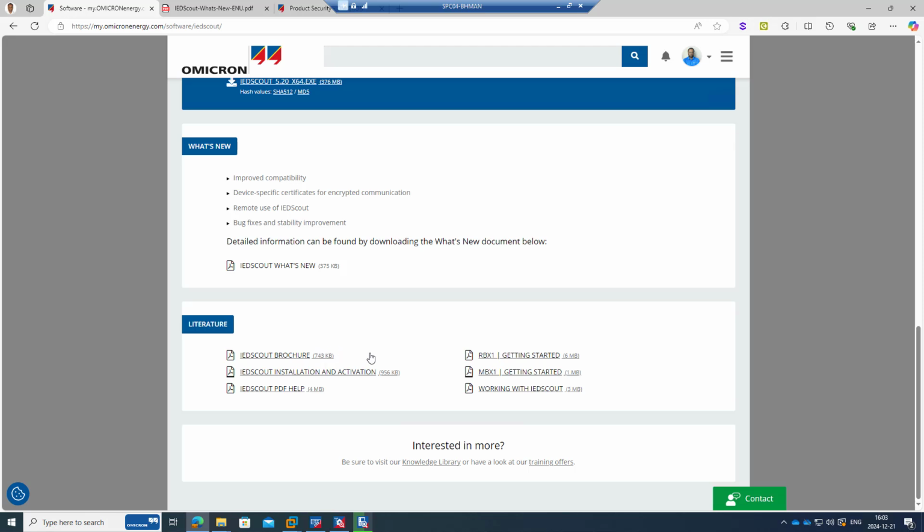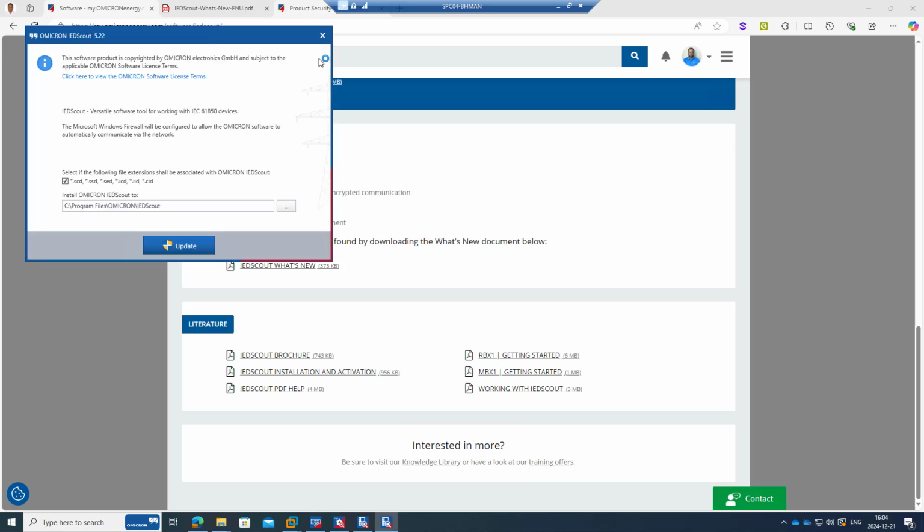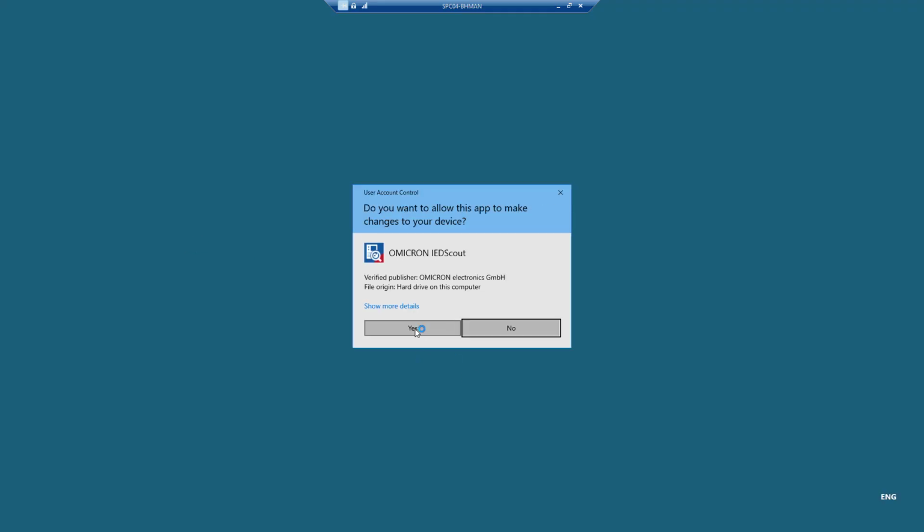There are some guidelines also available on how to proceed with installation, especially on the supporting software IEDScout requires in the backend, and PCAP for processing the network packets to translate them and make it easier for you when it comes to testing the client server and GOOSE messages with the IEDScout sniffer. So let's proceed with the update.